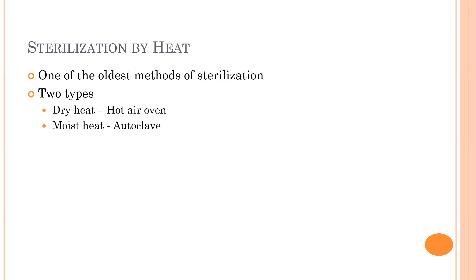So here you can see what is a hot air oven. Usually this is used for instruments which cannot be exposed to moisture. For example, you have some sharp metallic instruments which when exposed to moisture can get corroded, they can have rusting. So such kind of instruments you can use a dry heat sterilization. So basically you have a heating coil. This is similar to the heaters you use during the winter season in your rooms. They generate a dry heat. They do not include any humidity. So it is a dry heat, and there is usually a fan which is used to circulate the heat. And this dry heat causes protein denaturation and kills the microorganisms.